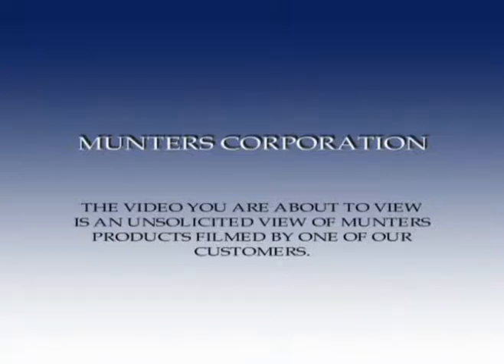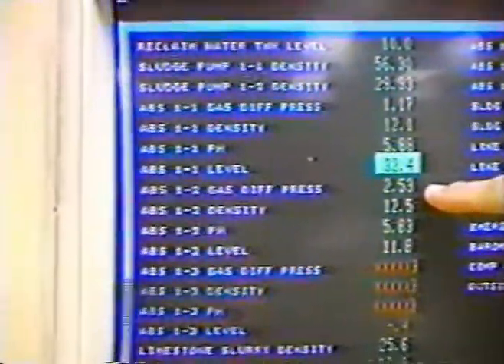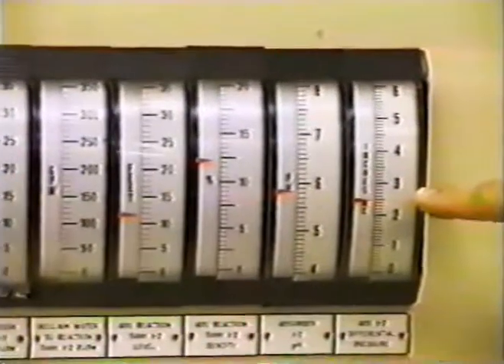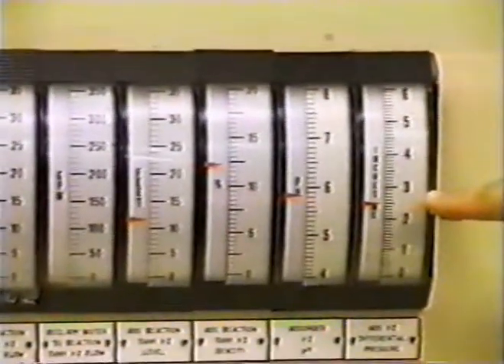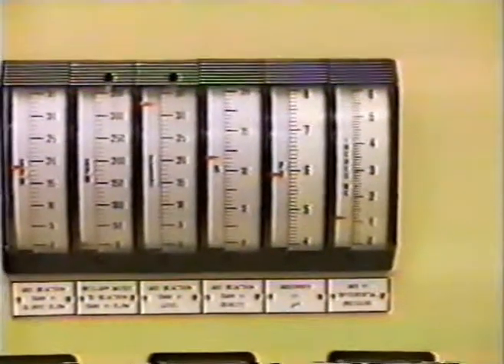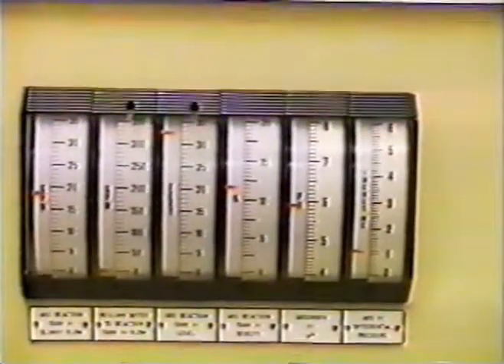As you can see, absorber 1 differential pressure is 1.17 as compared to the number 2 side, which is 2.53. That's a drop of more than an inch of delta P. You can also see here on the number 2 side on a moving scale, about 2.5 inches as compared to the number 1 side, which is a little over 1. This will result in horsepower savings on the ID fan and hopefully increase the absorber efficiency and reduce carryover.